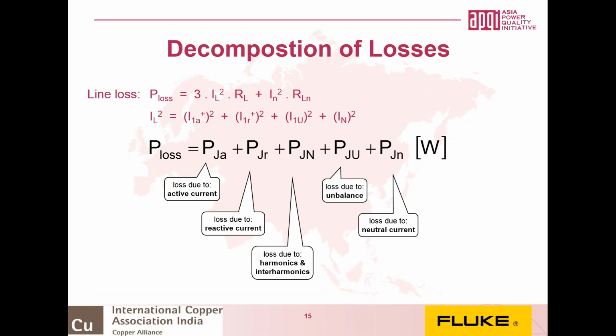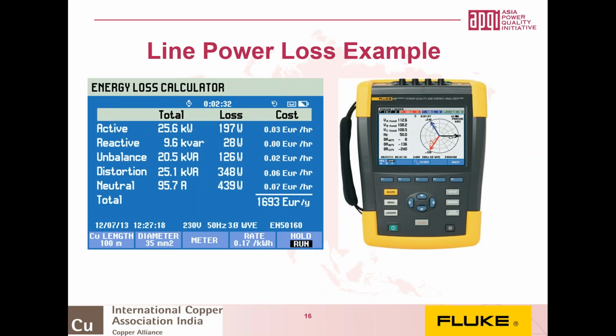So here we have a sample of an energy loss calculator that we've developed, and here we see the components broken down for each of the elements. First of all, we have the active power. In this case, we describe this based upon 25.6 kilowatts. This is based upon the length of the conductor that we're considering and the diameter and also the material, whether that's copper or aluminium. Then we have the reactive power, and again we have the same calculation of losses.